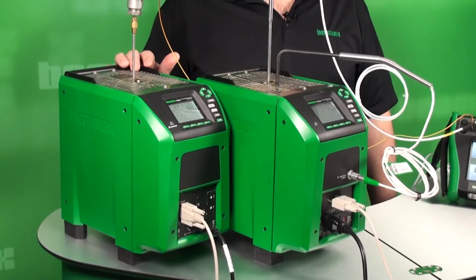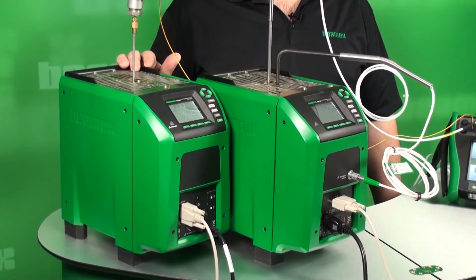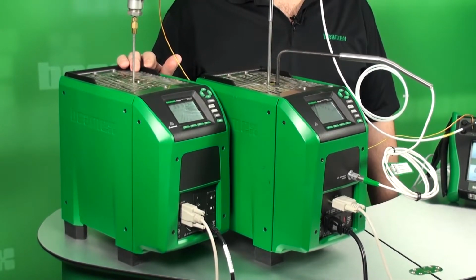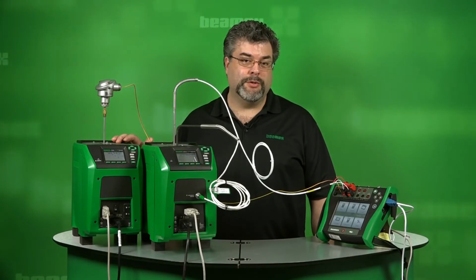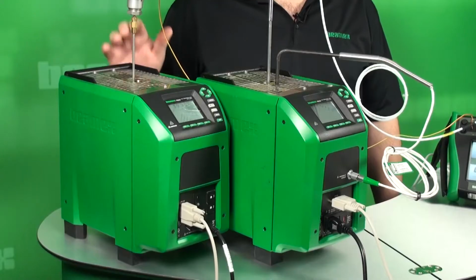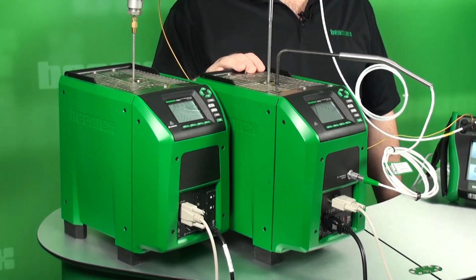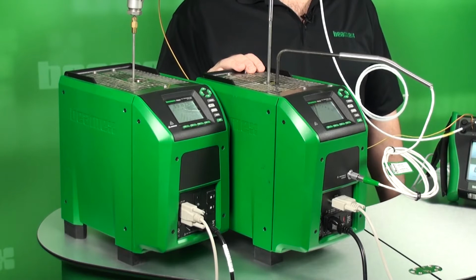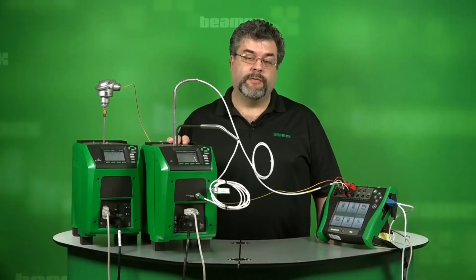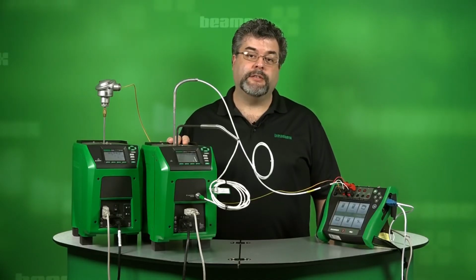First, I've got a Beamex FB660. This temperature block goes from 50 to 660 degrees Celsius. That's 122 to 1220 degrees Fahrenheit. The next block over is the FB150. This goes from minus 25 to 150 degrees Celsius. And the conversion on that is negative 13 to 300 degrees Fahrenheit.